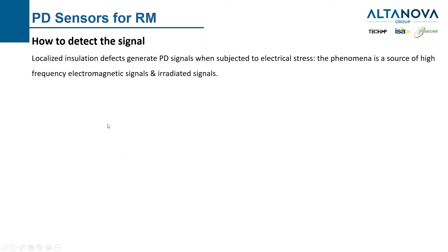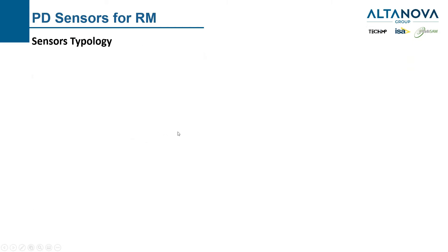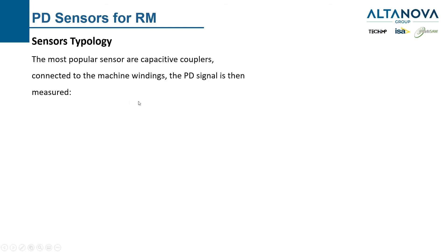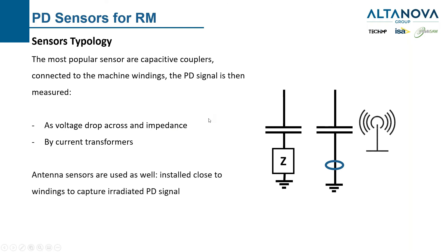How do we detect the signal? PD phenomena generate sources of high frequency electromagnetic signals — both conducted and irradiated. We can force the conducted signal to pass across our sensor, or we can try to measure it with antennas or other approaches. Different sensors will always give different output, different sensitivity, and they may or may not provide a synchronization signal. The most popular sensors are capacitive couplers, connected to the rotating machine connection, where the signal is measured either across a measuring impedance as a voltage drop or with a high frequency current transformer. There is also another solution using antenna sensors installed inside the stator to pick up irradiated signals.